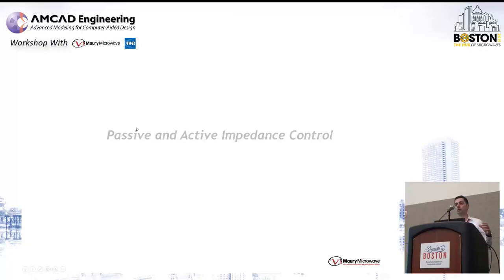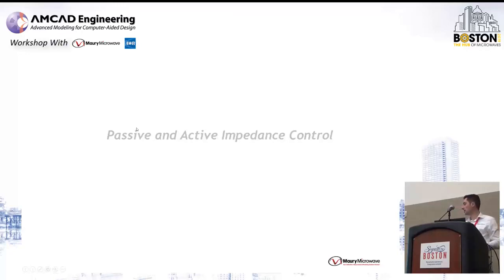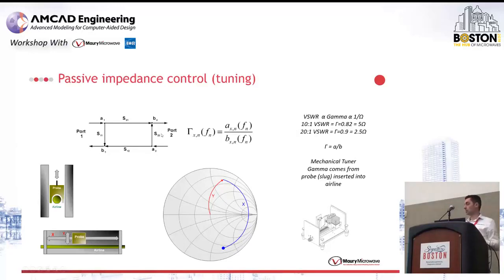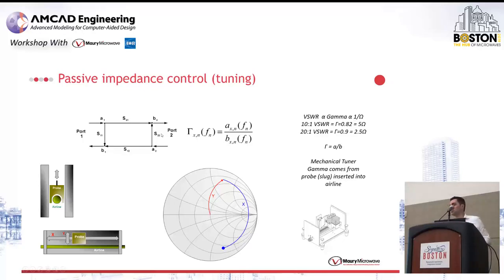There are several techniques, broadly split into two types of comparisons. In a load pull system there's the tuning part, where we compare passive systems versus active systems. The most probably known and simplest way of changing the impedance is using a passive mechanical tuner. Passive mechanical tuners are essentially airlines — mechanical instruments.